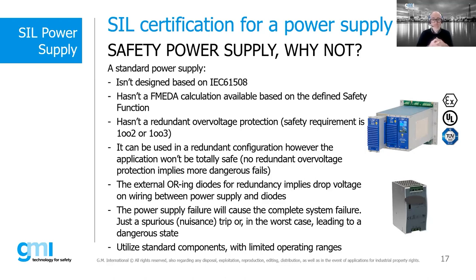As we have seen in the previous slide, a standard power supply is not designed based on the directive of IEC 61508. It does not have a calculation defined for the safety function to be obtained. It does not allow redundant protection from overvoltage issues, while in a safety power supply system, redundant protection is a fundamental requirement. And again, standard power supplies can be used in a redundant configuration, but they do not guarantee that our application is totally safe, for reasons related to common mode faults.